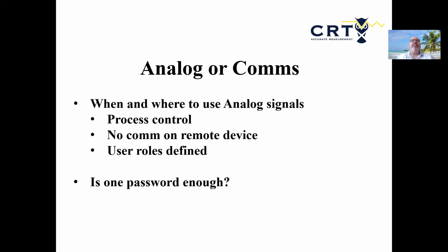Analog communications—basically, if I'm taking a temperature in as an analog signal versus communicating with the transmitter as a communication signal, what are the benefits and cons? The benefit of digital is that with an analog signal I typically have to scale it—I have to know what 4 milliamps equals, say 20 degrees, and what 20 milliamps equals, say 200 degrees. If my transmitter is scaled incorrectly, or the scaling in the flow computer is wrong, I can have a mismatch. Plus, I also have to calibrate that analog loop coming in.